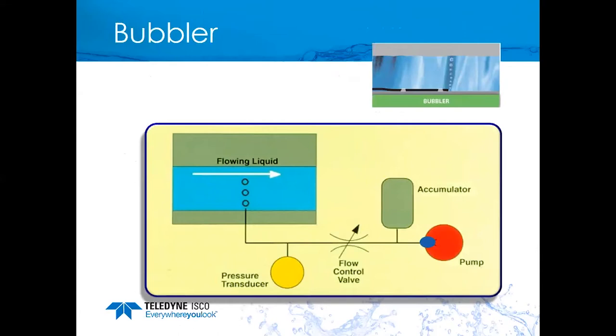The bubbler uses an air pump usually built into the meter. The pump builds pressure into an air tank then slowly releases it through a control valve at about one to two bubbles per second. A pressure transducer measures the pressure required to push out one bubble from the end of the bubble line. The higher the water height above the end of the bubble line, the more pressure required — which is directly related to the level.